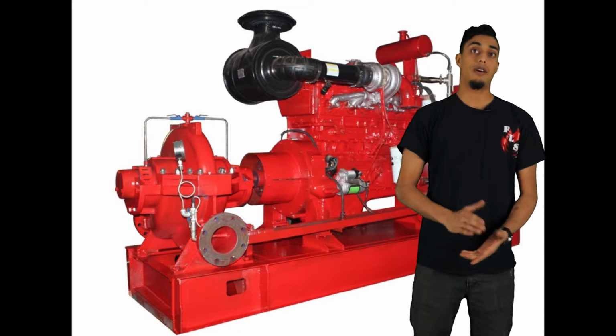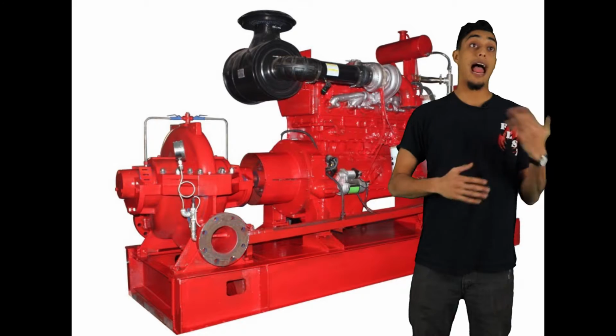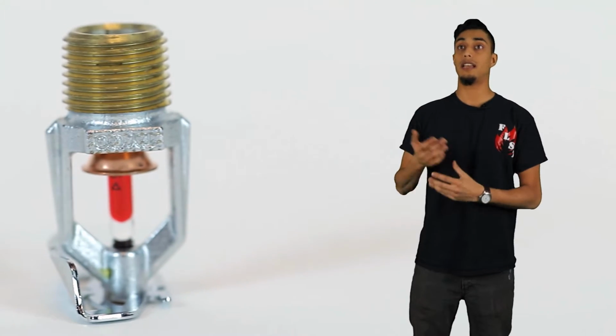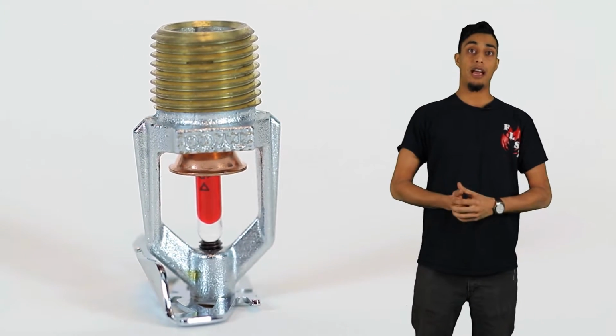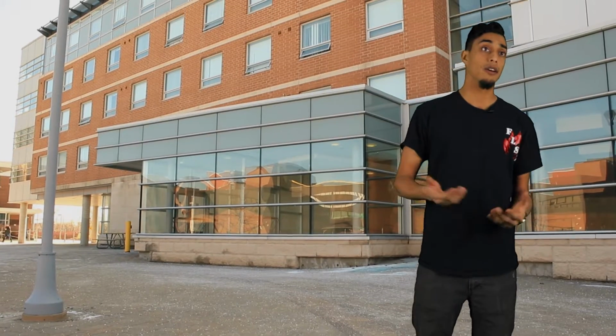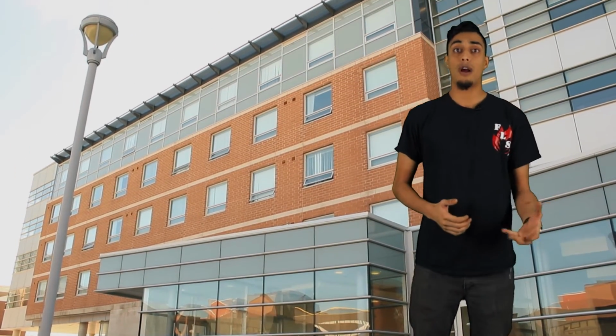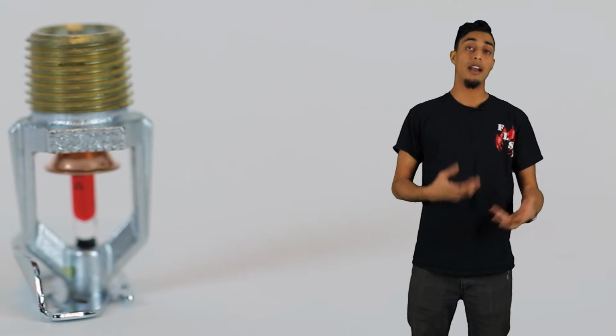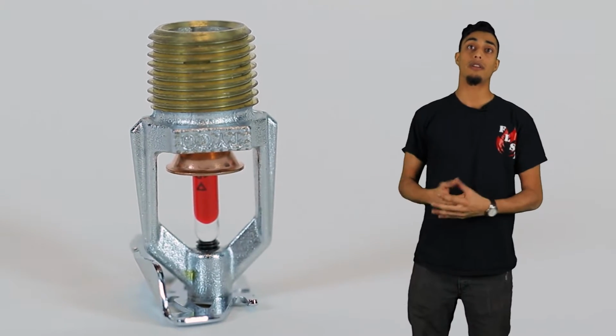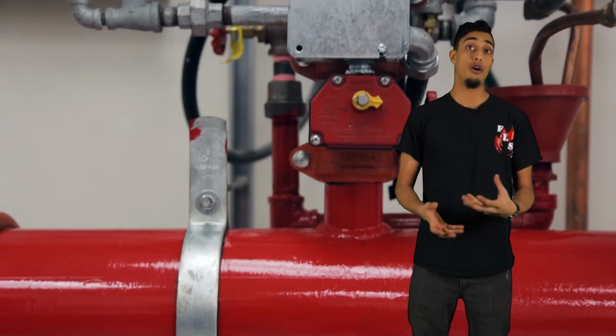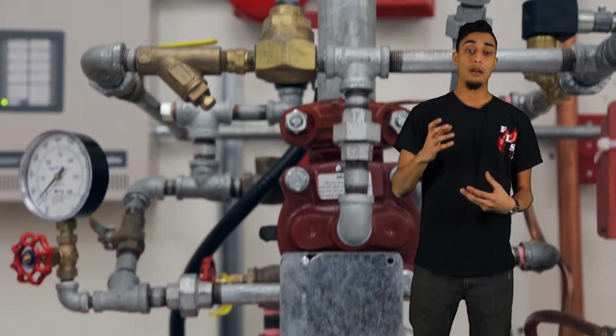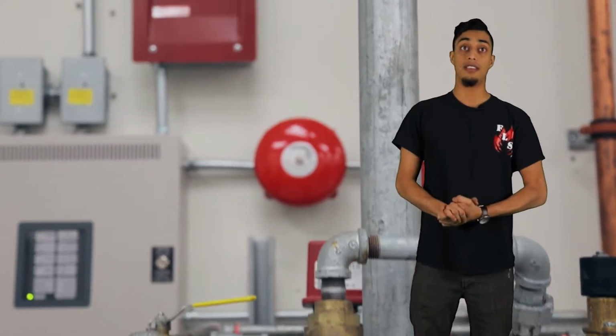Part 3. Testing a fire pump. Fire pumps are installed in our building to boost or add the water pressure that is available at any given sprinkler head. For example, a sprinkler head is located up on the 14th floor of a building. The city's water pressure would not be adequate or enough to be able to provide that sprinkler head with the level of water pressure it requires based on these NFPA standards.